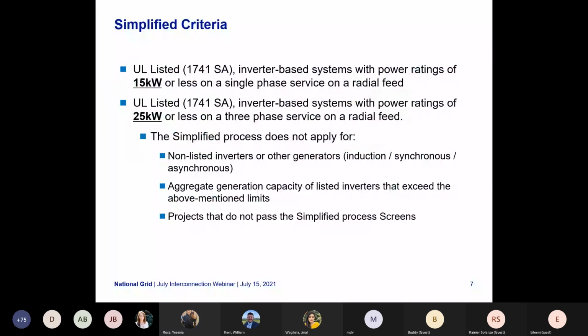I'm going to be going over the simplified process with you this morning. So on this slide, we'll just go through what the simplified process is. The simplified criteria consists of a UL listed 1741 SA inverter-based system with power rating of 15 kW or less on a single phase service on a radial feed, or a UL listed 1741 SA inverter-based system with the power rating of 25 kW on a three-phase service on a radial feed. The simplified process does not apply for non-listed inverters or other generators, aggregate generation capacity of listed inverters that exceed the above mentioned limits, or projects that do not pass the simplified process screen.